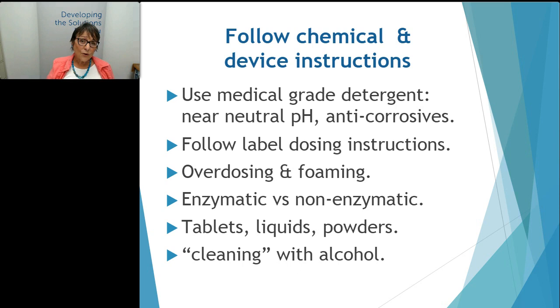If you overdose, thinking more is better, that's actually a problem because detergents leave residue. And if it's too hard to rinse the residue off, that residue will bake onto your instruments in the course of sterilization and then form layers over time. That's not good. So no overdosing. And also overdosing can lead to foaming, and foaming actually can inhibit cleaning when it's in the ultrasonic.